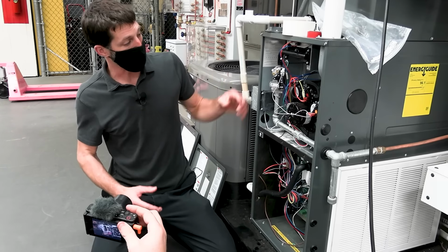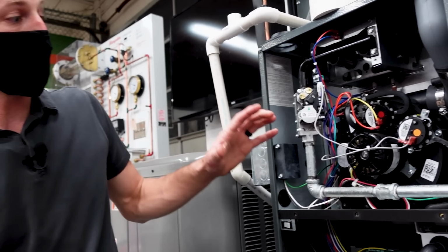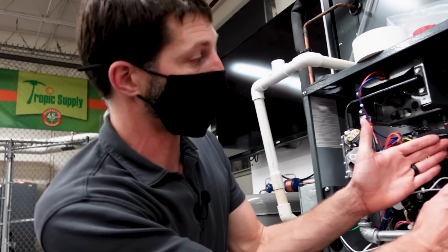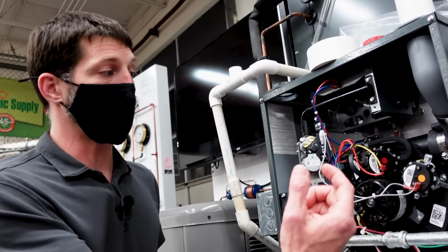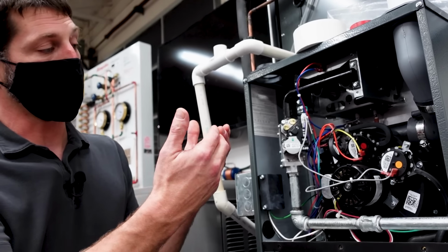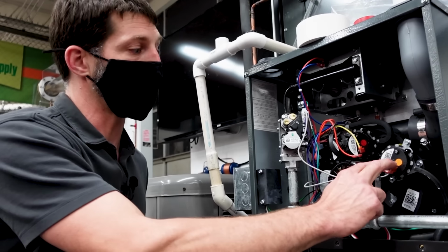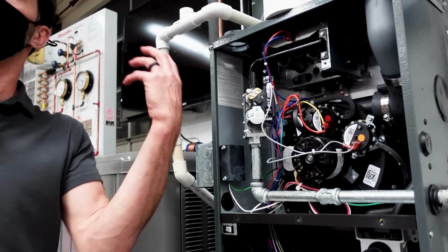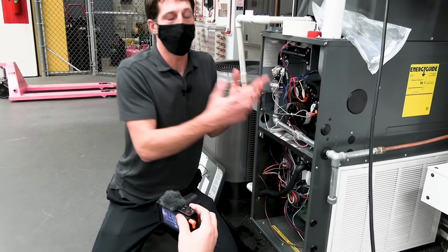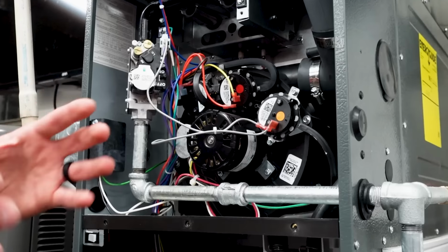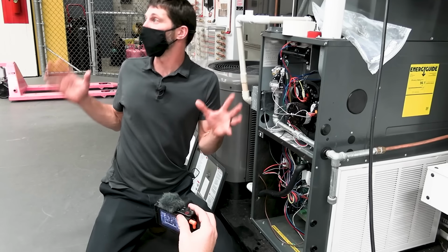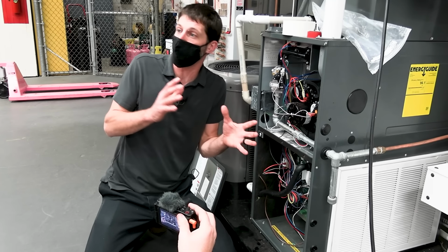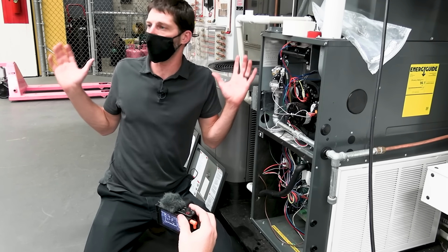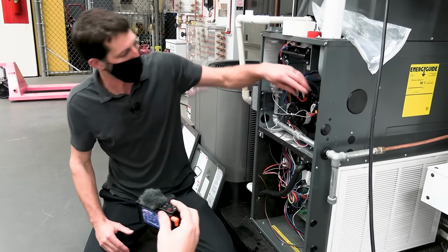If you ever suspect a pressure switch as being bad, you can basically turn the power off to the furnace and isolate that switch and connect it to your pump. Read the pressure readings, and you can take these electrical connections off and use either a multimeter or the wires that come with that tool, and you can test the pressure switch individually. I used to be nervous about, oh, it could be the pressure switch, I'm not sure. It takes all of the guesswork out of it, and it's really nice to have that tool.